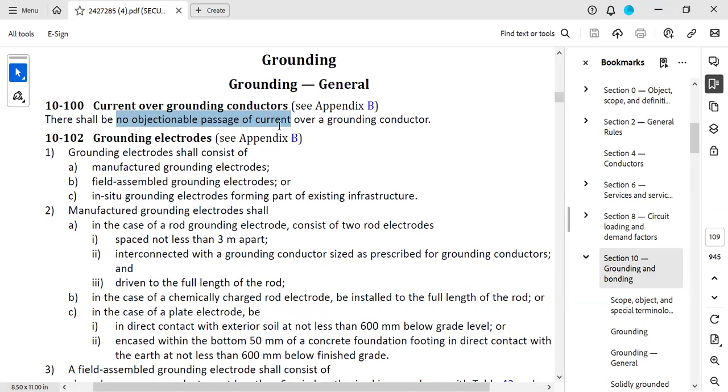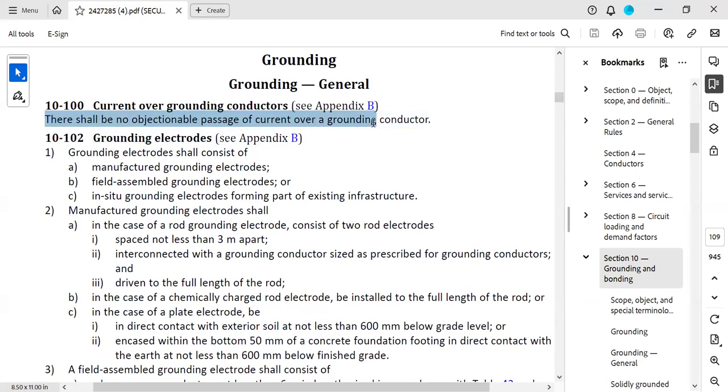The only currents that are not objectionable are those that occur under fault conditions, such as a temporary current resulting from a ground fault or the induced current from adjacent single conductors. So this is just one line of the code, but there's a lot of reasoning behind it. That's the reasoning behind Rule 100.